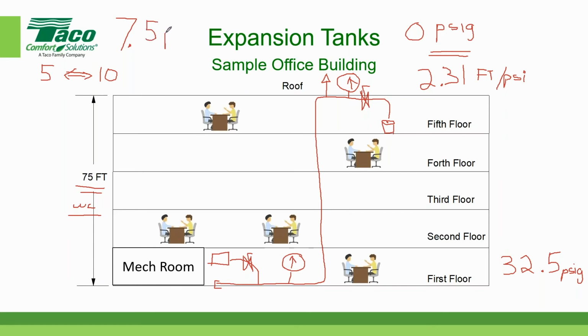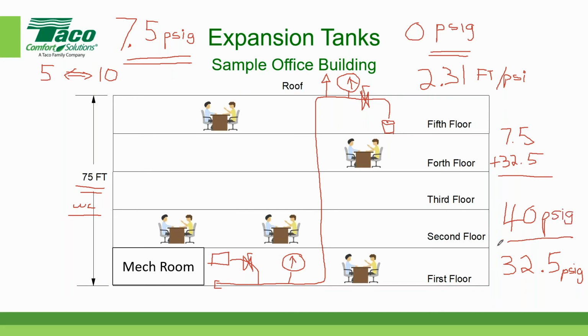And again, if someone wants to type in, if I add pressure so that I have 7.5 pounds at the top, what's my new pressure at the bottom of the building? 40, Scott said it, and Jean Luc too. We've got a lot of 40s. And it's simply 7.5 plus the 32.5. That's the pressure difference between the top and the bottom of the building, and that's equal to 40 PSIG. By the way, most of the folks typed in PSIG, so they're learning. Good crew. That's excellent.